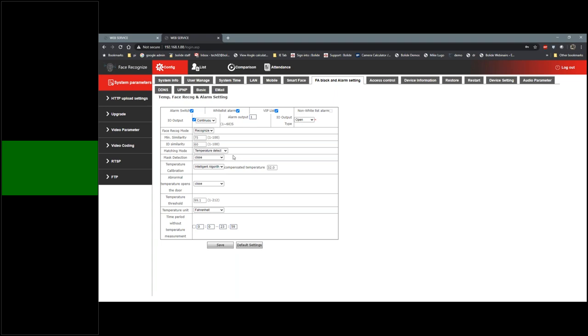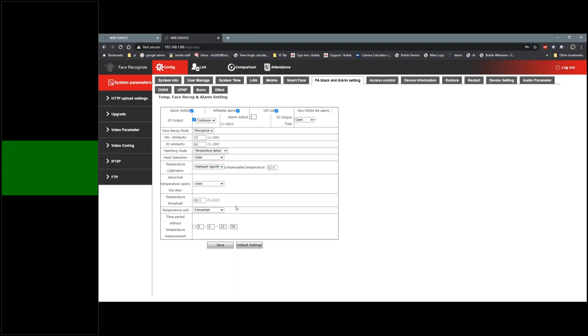The only thing you need to change here would be Fahrenheit to Celsius, depending on where you're using it. You can adjust the threshold — the temperature at which it sets alarms off. By default it's 99.1°F. Different states have different regulations on the minimum requirement. How does it read temperature? We use German IR detection — it's not thermal, so it does not need to be calibrated. The IR sensor gets accurate temperature off your skin. For this type of device, it's the way to go.